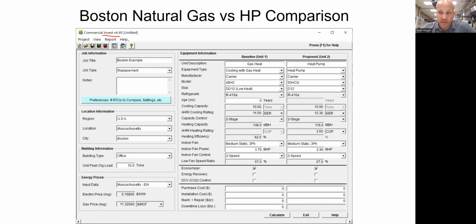If you're familiar with a software tool called Hourly Analysis Program, it's used for load estimating and robust energy modeling and stuff like that. This tool uses that engine, but what it does is it puts a bunch of assumptions in. Instead of making you energy model the whole building, which might take hours or days, you put a bunch of assumptions in, and this can do it basically in 5 minutes. It doesn't do the most awesome job of giving you the exact operating costs you're going to have. What it does do a great job of is showing you the difference between operating cost on choice A versus choice B. And that's really what I want in this scenario. I don't really care if it costs $1,000 to operate the old unit and $800 to operate the new unit. I just want to know that it's going to save $200 in operating costs from whatever I'm paying now, right? So I'm really concerned about the delta in this case. So the assumption thing is okay, not great, but okay. But it takes 5 minutes and not all day. So there's that trade-off.